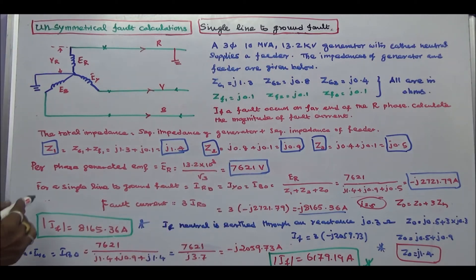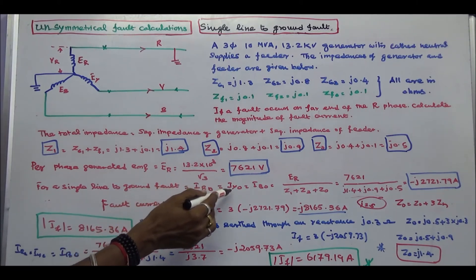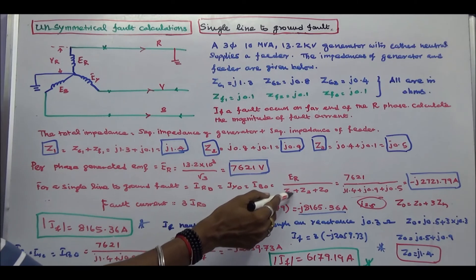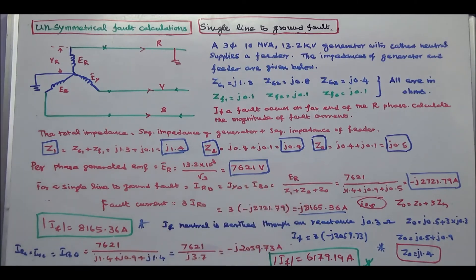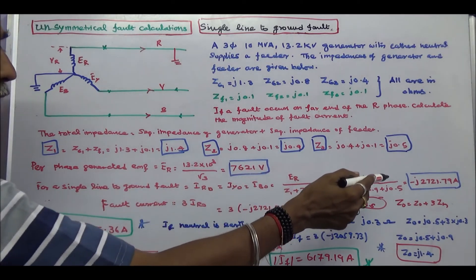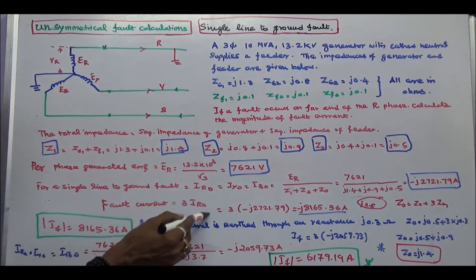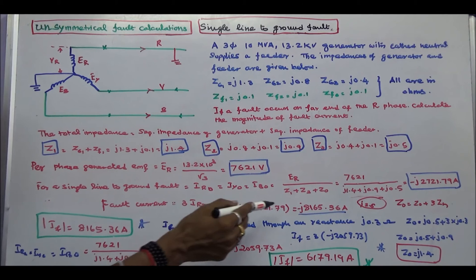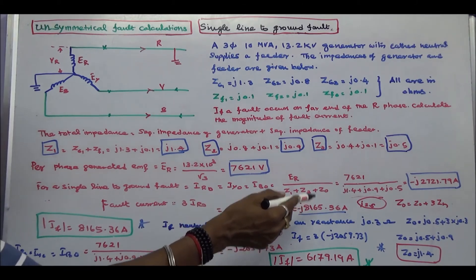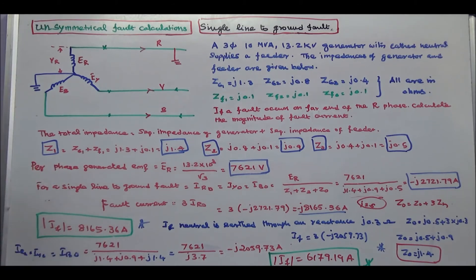We know that for a single line-to-ground fault, zero sequence current IR0 equals IY0 equals IB0 equals ER divided by (Z1 plus Z2 plus Z0). Substituting all values, the zero sequence current is −J2721.79 Amps. Fault current IF is 3 times the zero sequence current, that is −J8165.36 Amps. The magnitude of fault current is 8165.36 Amps.